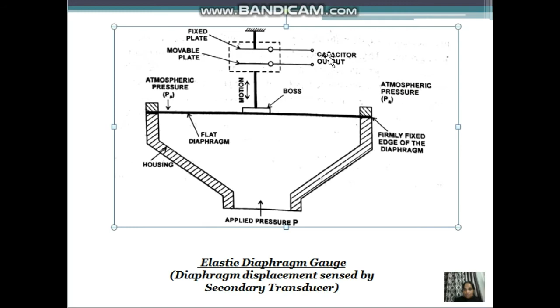Coming to the applications of the elastic diaphragm gauge, they are used to measure medium pressures, but they can also be used to measure lower pressures including vacuum in different conditions, and they are used to measure draft in chimneys or boilers. The main advantages are, by the construction, the cost is less, they have a linear scale of wide range, and they are safe to use with no permanent zero shift. They can measure absolute and gauge pressure and sometimes differential pressure also.